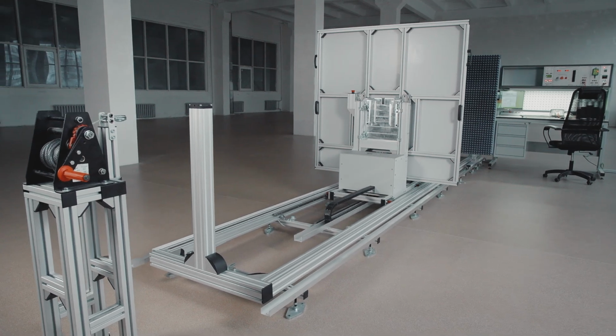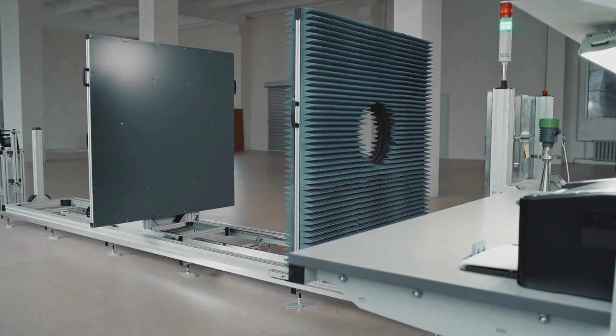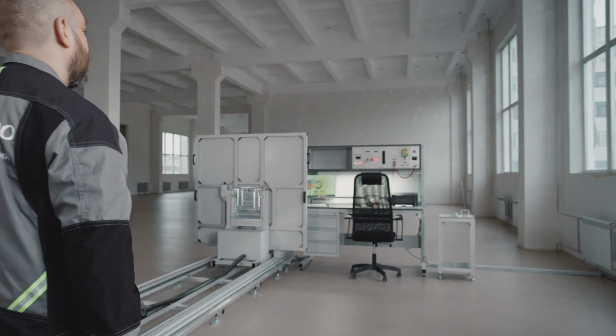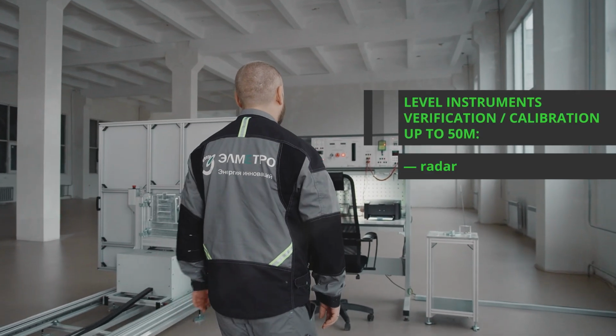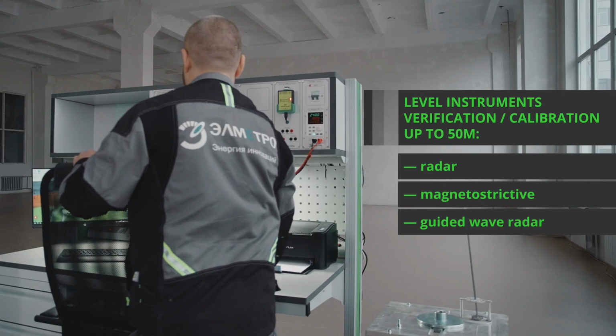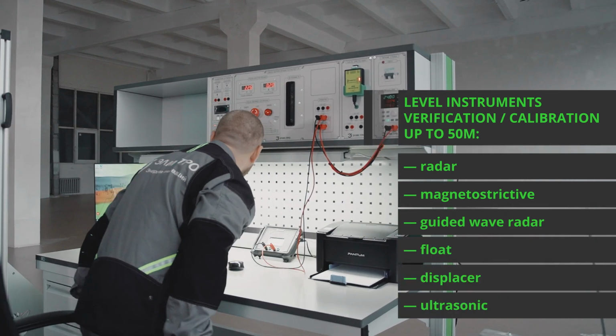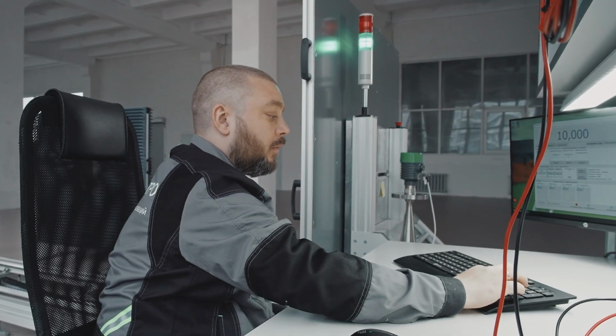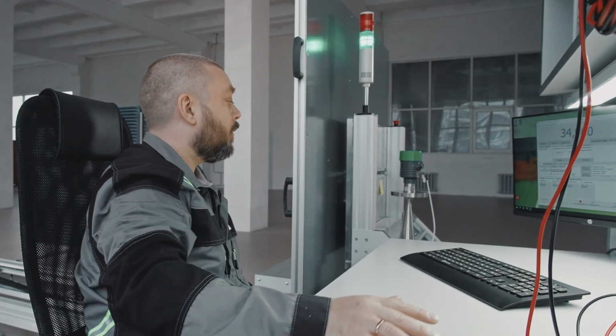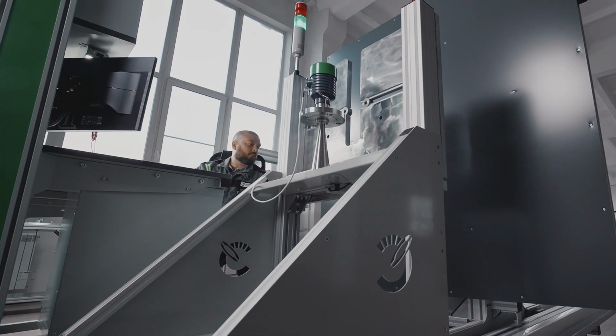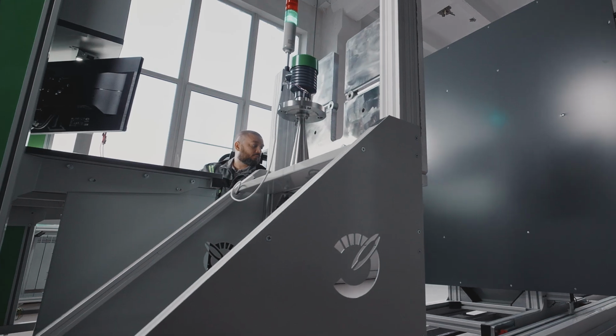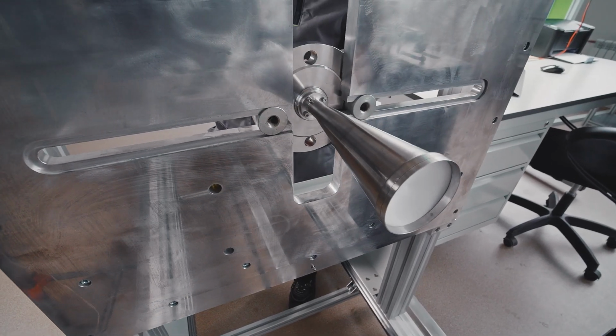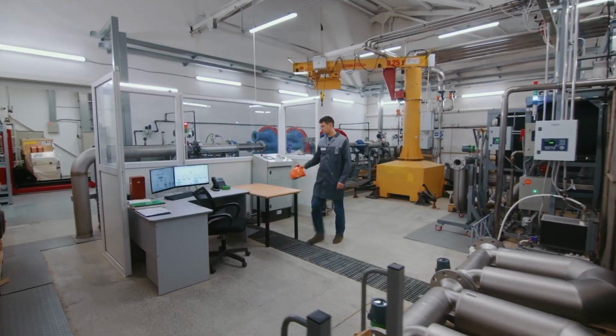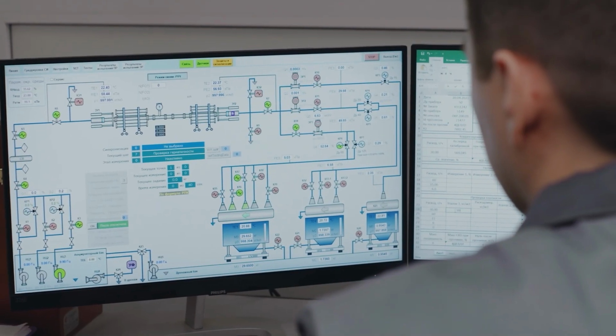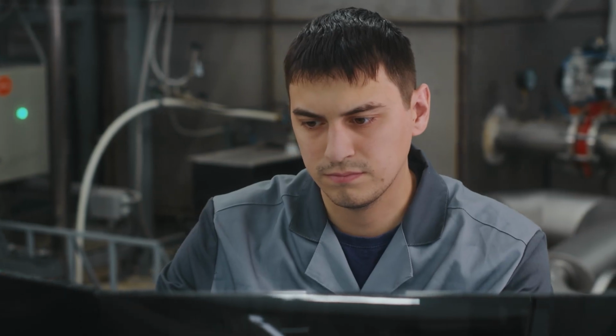ELMETRO-SPU bench is designed for automatic verification and calibration of level gauges of different types and measuring principles: radar, magnetostrictive, guided wave radar, float, displacer, and ultrasonic. One of the versions of our benches, ELMETRO-SPU-A, is used for verification and calibration of level instruments by simulation of liquid level measuring within the range reaching 50 meters. The ELMETRO experts analyze the gauges and the requirements of the client, the objectives and aims, industrial specifics.